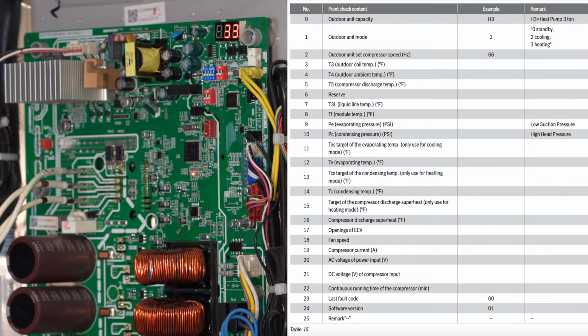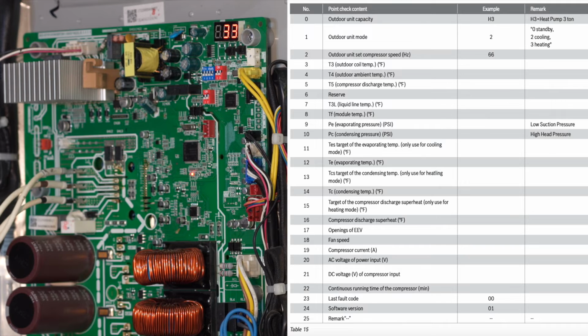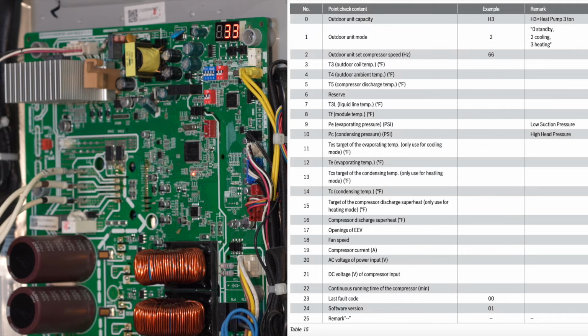And on my incoming power, number 20, that's my L1 and L2. It's telling me on number 20 we were getting about 198, 199 volts. Remember, once again, 172 to 270 is our operating range. 198 is within that, and we're in a kind of temporary scenario here.